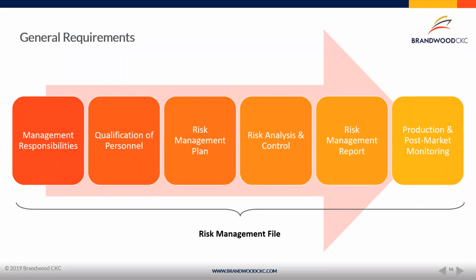That's in the risk management report because it tells a regulator, or anyone who's looking at your design dossier, your technical file, or your DHF, that there may be some residual risk. We've reduced them as much as possible, but we're still going to monitor those. In addition, these are the other ways that we get feedback so that we can keep this as an iterative process. And then finally, to add to that, production and post-market monitoring is an absolute requirement for every regulatory jurisdiction: you have to have post-market monitoring of your device.